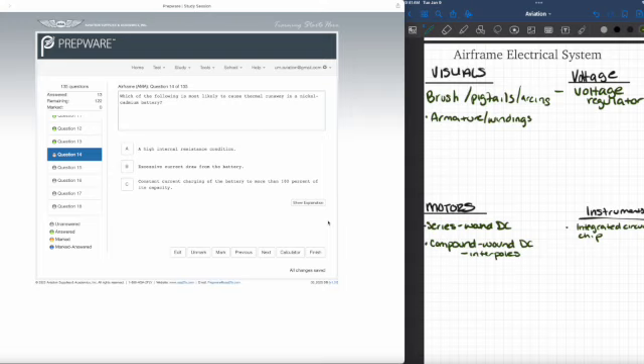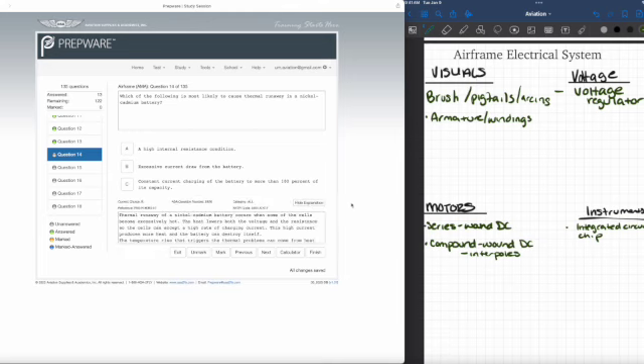Which of the following is most likely to cause thermal runaway in a nickel-cadmium battery? A. A high internal resistance condition. B. Excessive current draw from the battery. Or C. Constant current charging of the battery to more than 100% of its capacity. The answer is excessive current draw from the battery. Thermal runaway of a nickel-cadmium battery occurs when some of the cells become excessively hot. The heat lowers both the voltage and the resistance, so the cells can accept a high rate of charging current. This high current produces more heat and the battery can destroy itself. The temperature rise that triggers the thermal problems can come from heat generated by a fast discharge, from high ambient temperature, or from a breakdown of separator material.